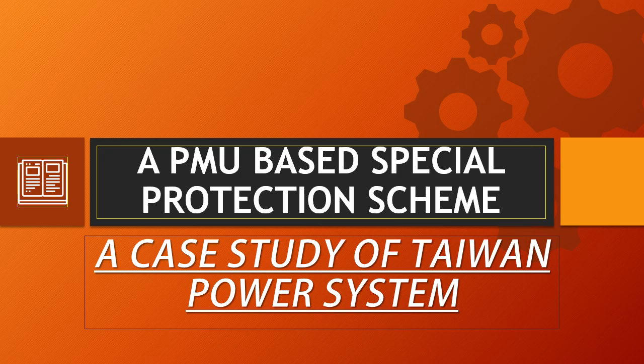phasor measurement units. In a control center, we use PMUs to monitor the generators and the major EHV transmission lines of a power system and apply an instability protection algorithm for initiating a special protection scheme to avoid a sequence of related events whenever necessary. When a fault happens, we group the generators swinging coherently and reduce the system to one machine infinite bus system. The remedial control actions consist of load shedding and generator tripping.